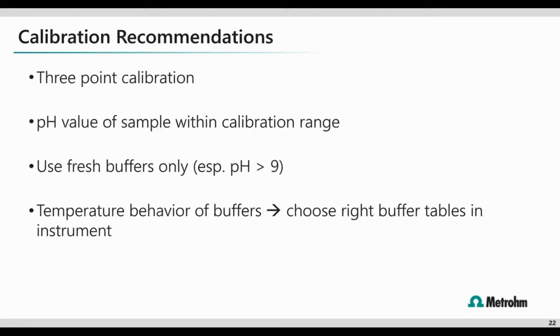General calibration recommendations: use a 3-point or 3-buffer calibration. When you're selecting buffers to make your calibration, select ones that bracket the pH range of the samples you're measuring. It's important to use fresh buffers, especially in the higher concentration ranges. Anything over pH 9 will start to absorb CO2, and that will alter the value. And then lastly, make sure we're selecting the right buffer in the instrument and either enter that temperature measurement manually or set it to automatic or continuous for temperature correction.